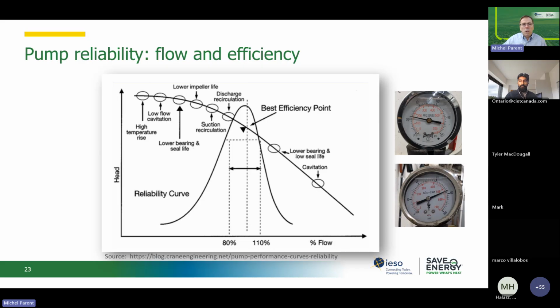That's one way to make sure the pump is the right size for your loop, for your building: throttle the pump. The other way is to put a VFD on the pump. Doesn't mean it's going to be properly sized, though. You also need to measure, under the normal VFD speed operation, the more common one, what the delta P is across that pump. Now you check that delta P against the nameplate delta P. If you're dead on, so you got exactly the head that was supposed to be, your pump is running at its best efficiency point. And that's what you want.